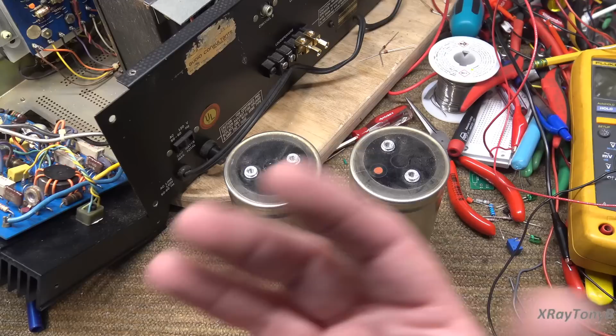Once the capacitors charge up a little, the inrush current will begin to drop. That initial shot of current, called inrush current, can be very significant. For capacitors, amplifiers, and transformers like this, it's not uncommon to see an inrush current, just for a split second, of over 100 amps.